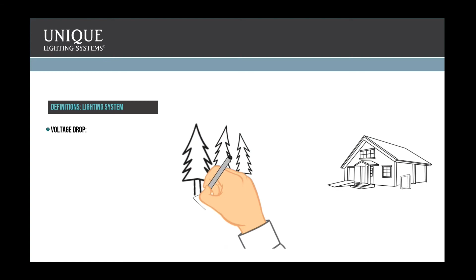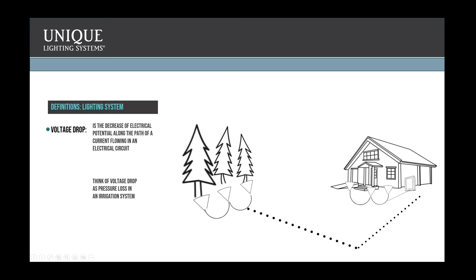Now one of the things we need to understand when designing low voltage systems is voltage drop. Voltage drop is nothing more than the decrease of electrical potential along the path of current flowing in an electrical circuit. We can think of voltage drop as pressure loss in an irrigation system. Looking at our diagram, we have our house and a transformer, with a zone of lights close to the house, and maybe some trees quite a distance away. So the wire run connecting those distant lights is much longer, meaning we have much more resistance or voltage drop on that run.